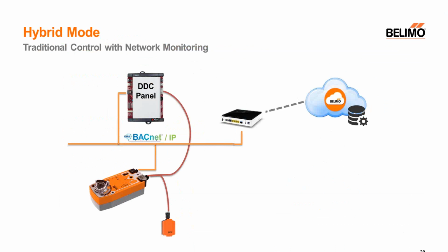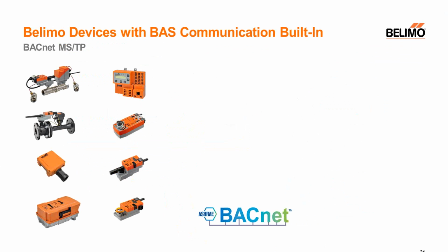And then we do offer an additional type of setup on these actuators. Instead of connecting two sensors, if you want to control the actuator in a traditional way, using like a 2 to 10 volt signal coming out of your DDC panel to tell it what position to go to, you can do that. You configure one of the sensors as a set point, a position set point input, and then you can use the other one as a process value, like a temperature or humidity or whatever you want to monitor. And you can still see that all via the cloud, and you can actually override how the actuator is working from the cloud. That's called hybrid mode.